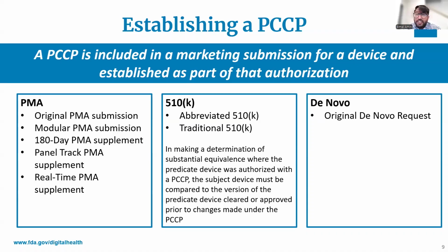Depending on your device, this could be a 510(k) submission, a de novo request, or a PMA, including certain PMA supplements listed above. One nuance I want to flag for those of you thinking about the 510(k) pathway is if you're using a predicate device that itself has an authorized PCCP, you need to compare your device to the version of the predicate before any changes were made under that PCCP, not the current version, the original authorized version.